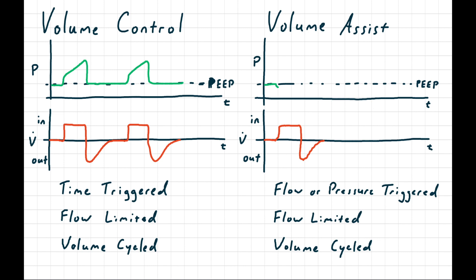That triggers the ventilator to start its normal volume control breath with a set tidal volume delivered at a constant flow rate. Then the ventilator will sit and wait to be triggered by another patient breath effort. If the patient wants to breathe again one second later or eight seconds later, it happens again — flow will start to rise a little bit, pressure will drop a little bit due to the patient's inspiratory effort, and the ventilator will immediately trigger another flow-limited breath. The trigger is different in volume assist mode: we are flow or pressure triggered instead of time triggered.